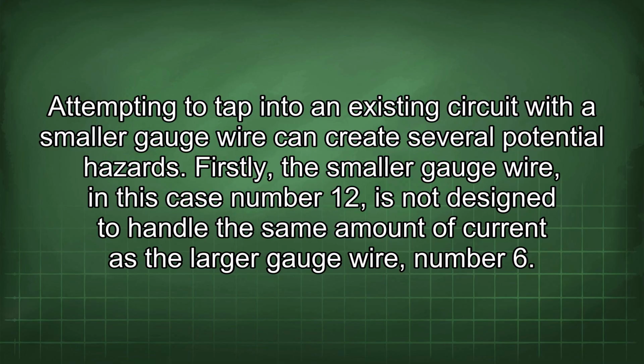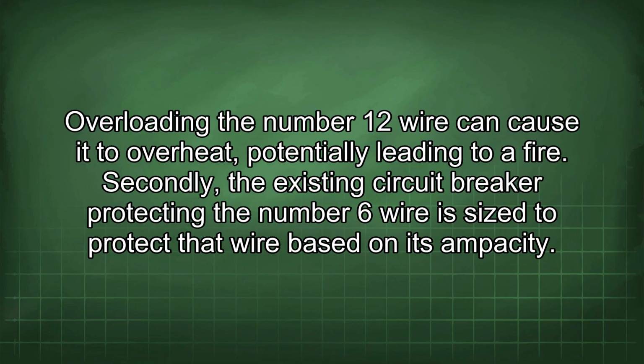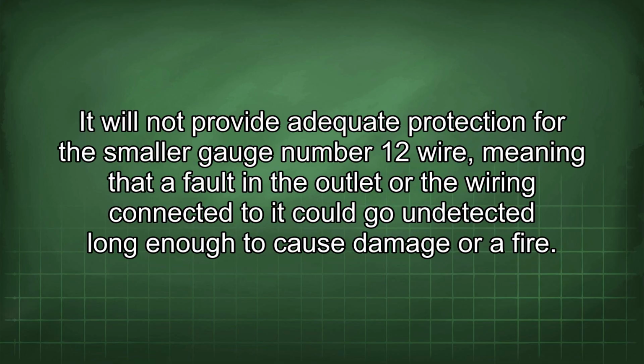Firstly, the smaller gauge wire, in this case number 12, is not designed to handle the same amount of current as the larger gauge wire, number 6. Overloading the number 12 wire can cause it to overheat, potentially leading to a fire. Secondly, the existing circuit breaker protecting the number 6 wire is sized to protect that wire based on its ampacity. It will not provide adequate protection for the smaller gauge number 12 wire, meaning that a fault in the outlet or the wiring connected to it could go undetected long enough to cause damage or a fire.